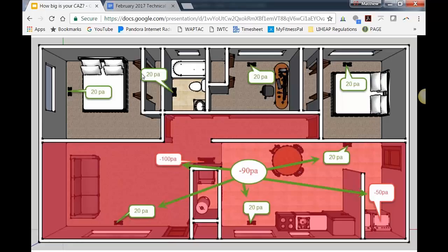And so they ended up turning up the exhaust fan, which started drawing more air out of the home and caused the appliance to fail. Anyway, it was just interesting, and we went back through every single step. They did everything correct other than they should have adjusted the exhaust fan and then conducted their final test.